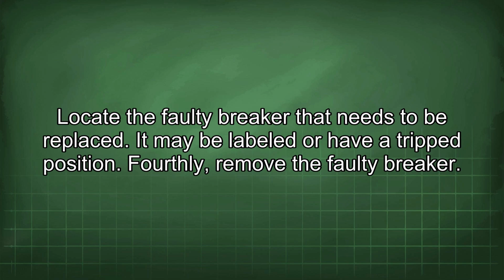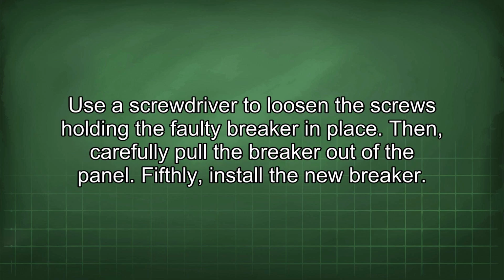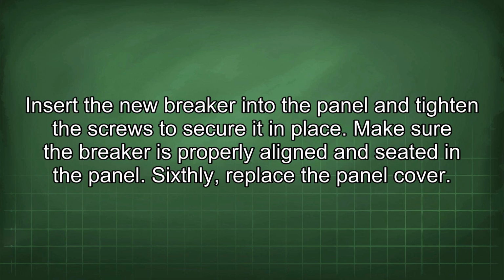Fourthly, remove the faulty breaker. Use a screwdriver to loosen the screws holding the faulty breaker in place. Then carefully pull the breaker out of the panel. Fifthly, install the new breaker. Insert the new breaker into the panel and tighten the screws to secure it in place. Make sure the breaker is properly aligned and seated in the panel.